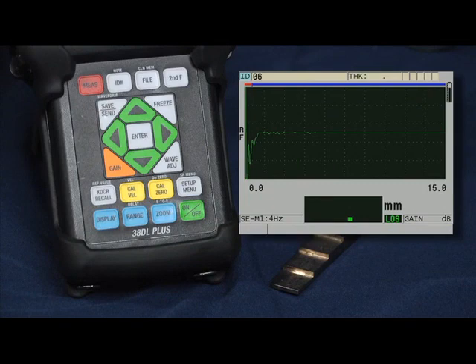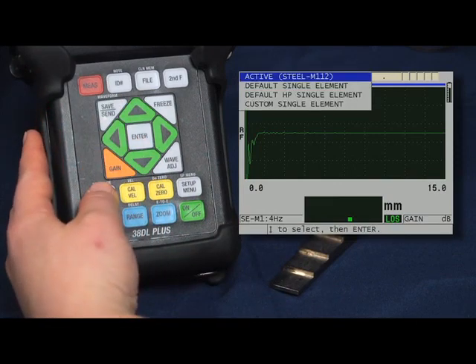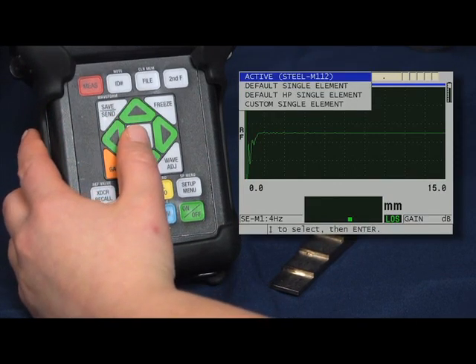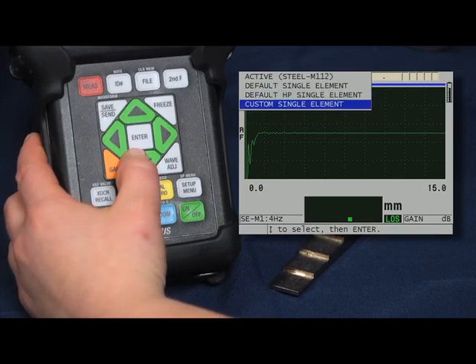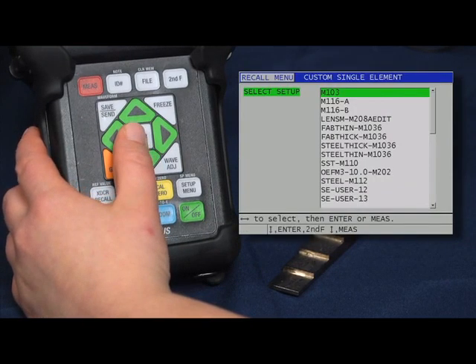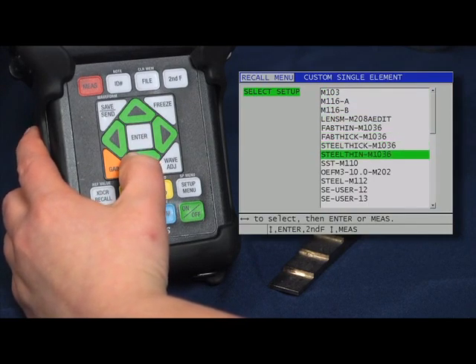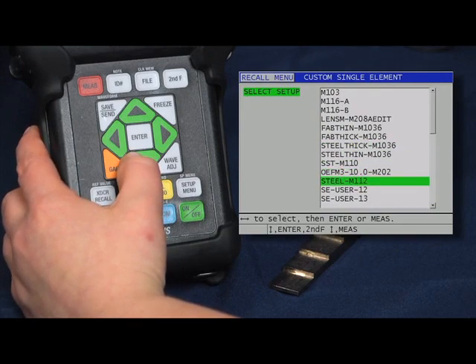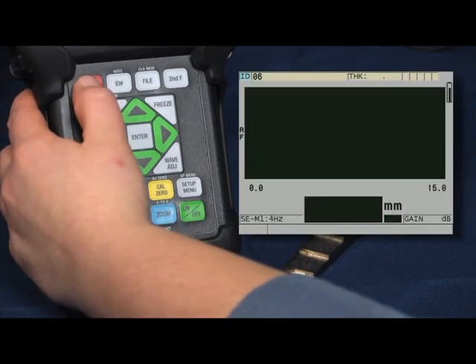Now that we have stored our calibration as a custom transducer setup, it can be recalled at any time on the 38DLplus. To recall a custom transducer setup, simply press the transducer recall key, then use the down arrow key to scroll down to custom single element and press the Enter key. Here in this list, you will see your custom transducer setup that can be easily recalled by using the up or down arrow key to highlight it and press the red measure key to recall the setup to start making measurements. This completes our session on how to recall, calibrate, and store a single element transducer setup on the 38DLplus.